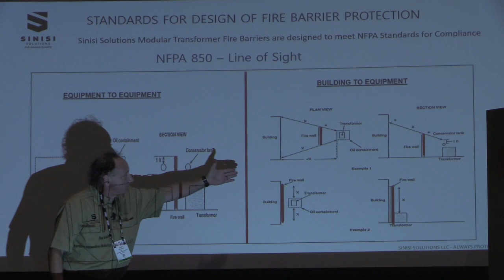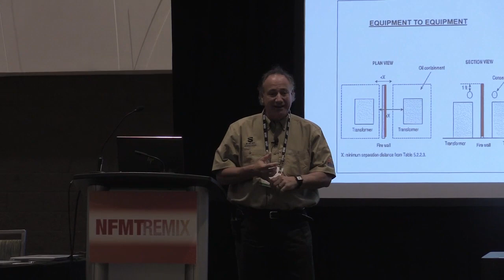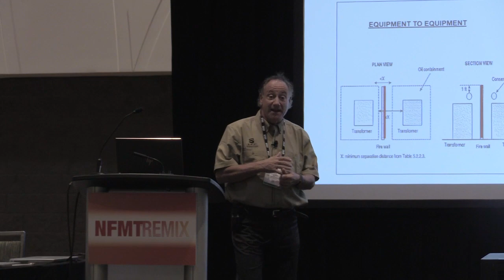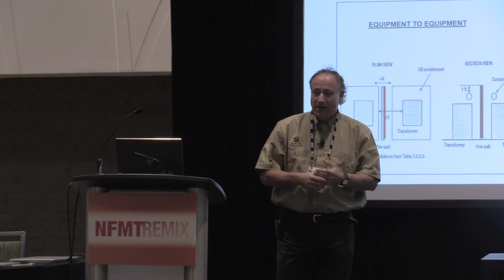If you have a transformer near a building, probably if you're within 50 feet, you're required to have a fire barrier. Many of the new properties, everything is kind of squished together. The architects don't have as much room, they put things in smaller places, they wind up next to buildings. Senior care centers - I can't tell you how many times - long-term care facilities have transformers and generators right next to the building.